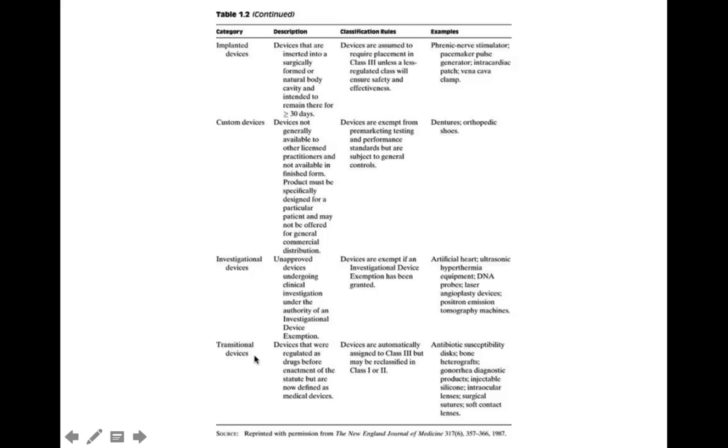And then transitional devices, these were regulated as drugs before, and now they're defined as medical devices, and so that would be things like injectable silicone, intraocular lenses, surgical sutures, soft contact lenses, and the like. So those are a few of the general categories that the regulatory environment considers. And so that gives you something to consider when you think about device design.